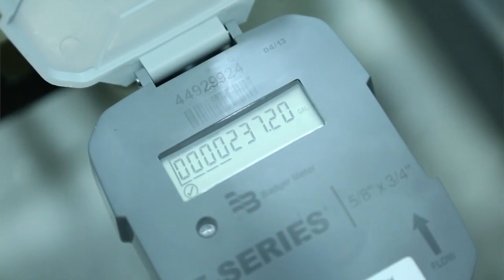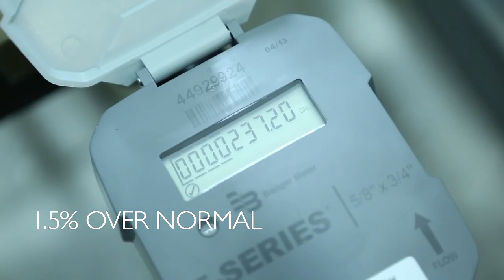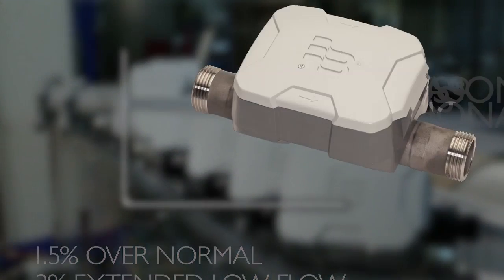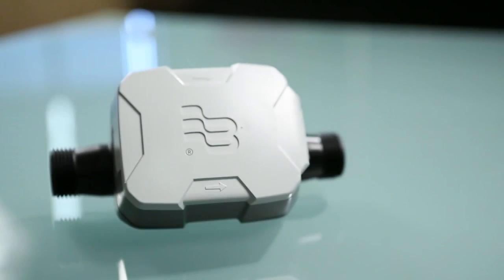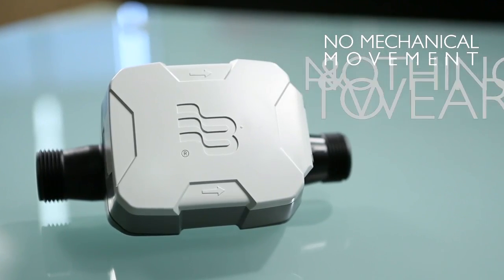That information is highly accurate — to within 1.5% over the normal operating range of the meter, and within 2% at extended low flows. E-Series Meters have the same high, out-of-box performance as their RecordAll counterpart, but are warranted to maintain their accuracy over time because there's no mechanical movement and nothing to wear.